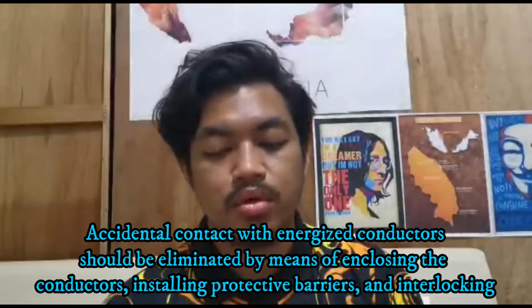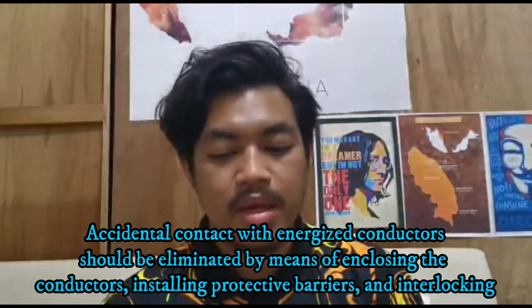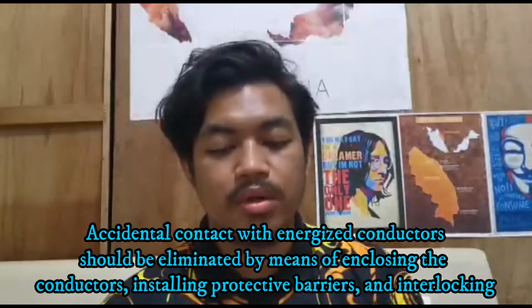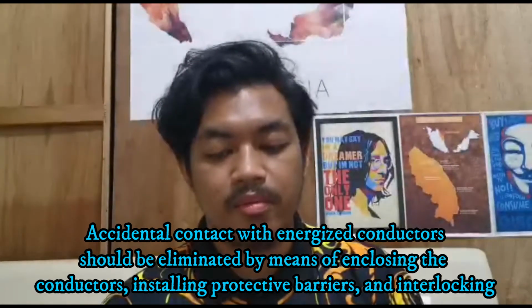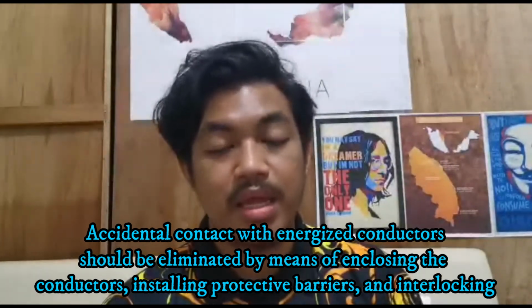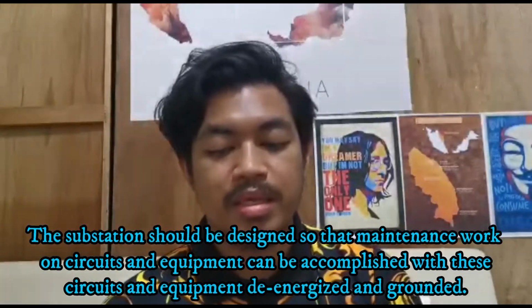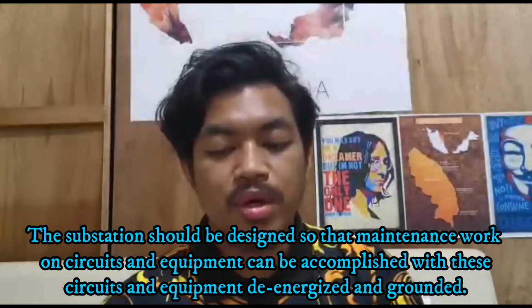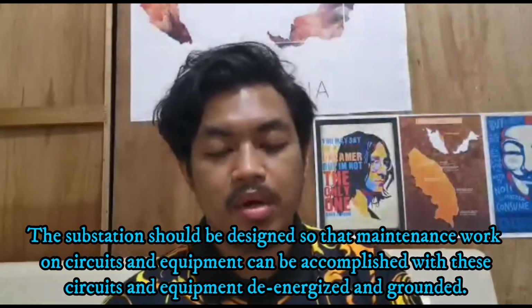Next, accidental contact with energized conductors should be eliminated by enclosing the conductor, installing protective barriers and interlocking. The third one, the substation should be designed so that maintenance work on circuits and equipment can be accomplished with the circuits and equipment de-energized and grounded.